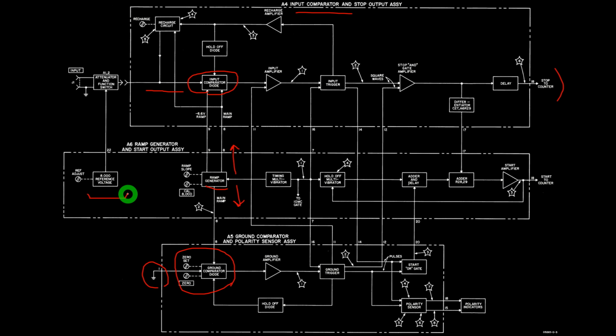There's also the 8-volt reference, which also has an adjustment, and that can be directly fed into the input switch. When you select the input, one of the scales you can select is the 8-volt, and that injects the 8-volt directly into the comparator, allowing you to calibrate as well. That's important because these ramp generators and everything else are going to drift, and one way to establish the references is the 0 and the 8-volt.